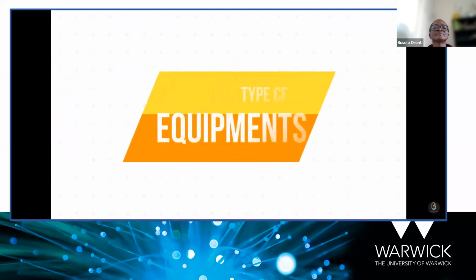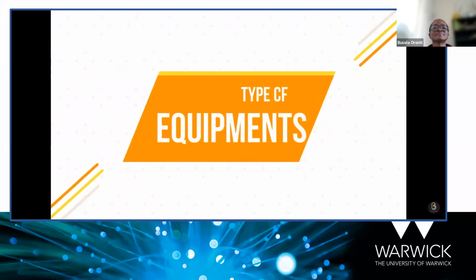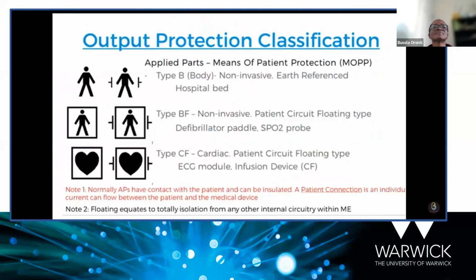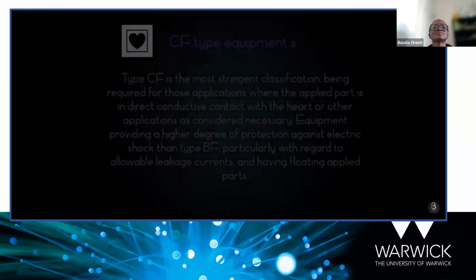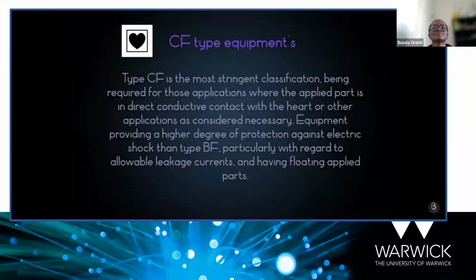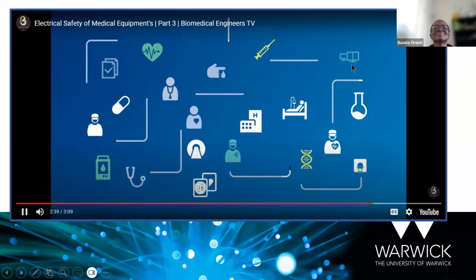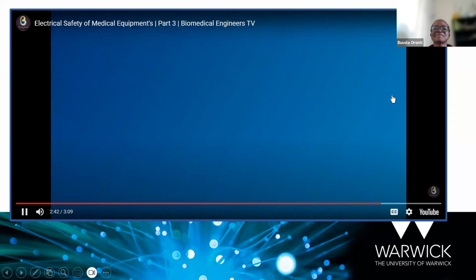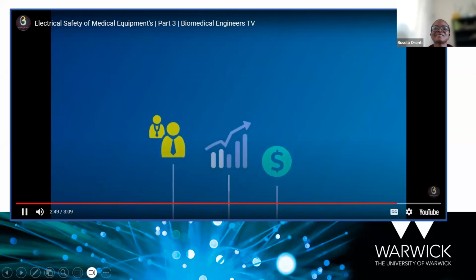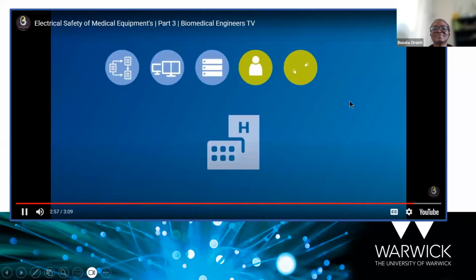And the last one is the CF type equipments. Type CF is the most stringent classification, being required for those applications where the applied part is in direct conductive contact with the heart or other applications as considered necessary. Equipment providing a higher degree of protection against electric shock than Type BF, particularly with regard to allowable leakage currents and having floating applied parts. I hope you understood the electrical safety standards of medical equipment in a simple manner. I request please go through the testing process as per the electrical safety device procedure, as every manufacturer has their own protocols. Thanks for watching, and don't forget, subscribe the channel. Right. See you guys.